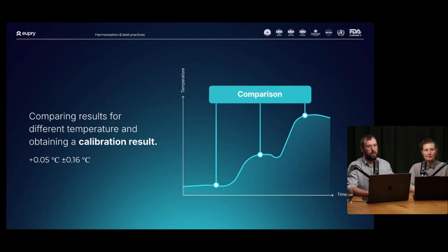So what you do is that you compare at different points, and we'll go into the importance of having several different calibration points. And what you'll obtain is a calibration result. So a calibration result shows how different the reference and the device under calibration are. So in this example, 0.05 degrees Celsius off. So that means if you're using this device under calibration, it will show 0.05 degrees off. So it will measure a little bit more than what the reference does.